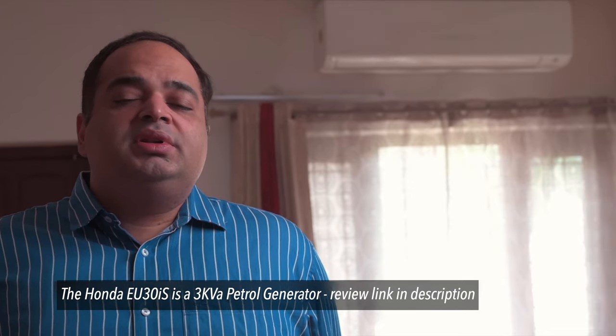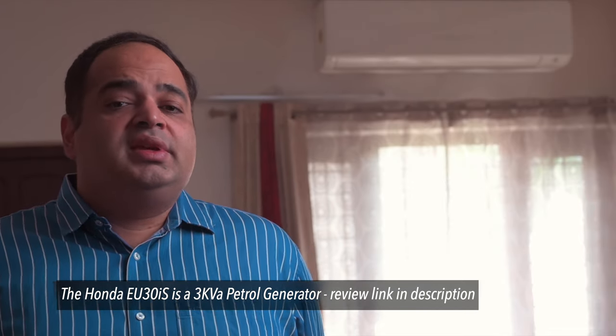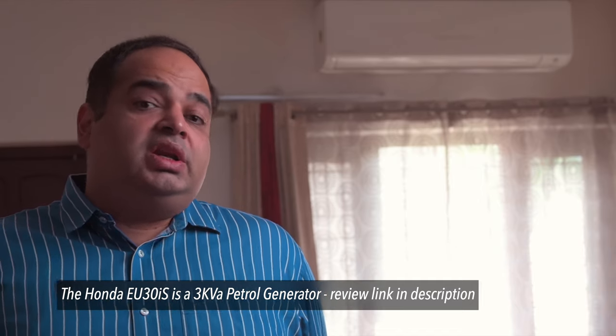I have also tried to run it on my small Honda EU30IS generator and it performs very well. Even at the full power setting, the generator was able to run this 2.3 ton AC without any problems. This generator can also run a non-inverter 5 star fixed speed AC, but the surge power those air conditioners require when they start up really makes the generator struggle initially — surge power goes up to 3,600 watts. None of these problems with the Mitsubishi Heavy Industries inverter AC. This 2.3 ton AC slowly eases into full power consumption, making it ideally suited to even a small 3 kVA generator.